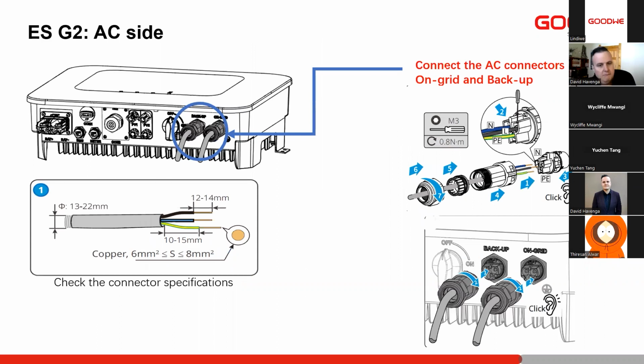On the AC side, you really need to make sure to plug the correct cables into the correct ports. You've got a backup port, which is for your essential loads, and then the on-grid port, which is for your grid connection, your bidirectional grid connection. Always make sure that you put the grid connection in the on-grid port, because if you plug the grid into the backup, you can cause the device to fail because you're injecting voltage into an output port. So always verify before you connect it to the device that you put the correct one in.